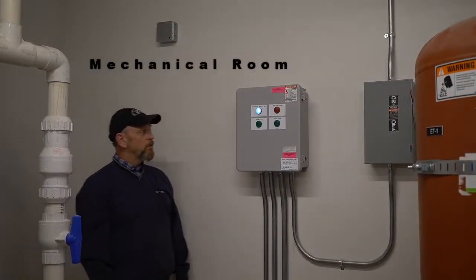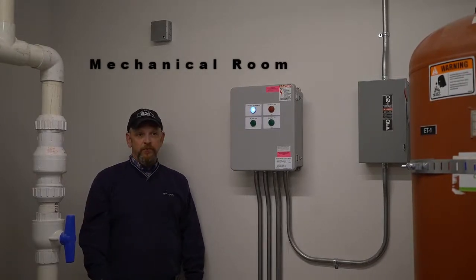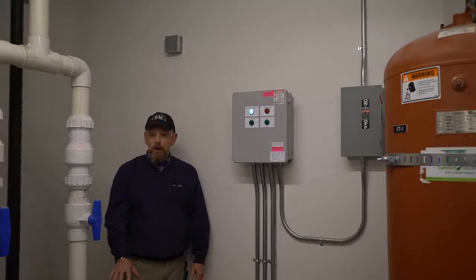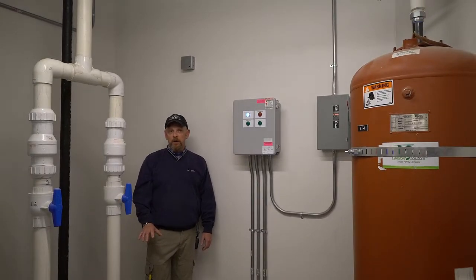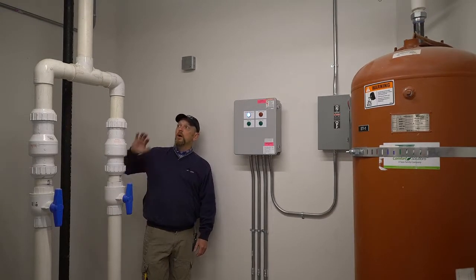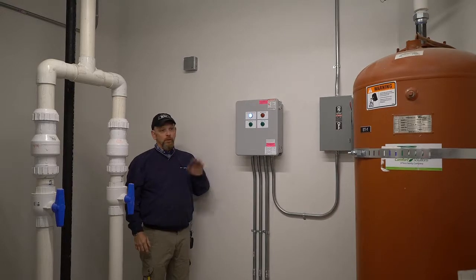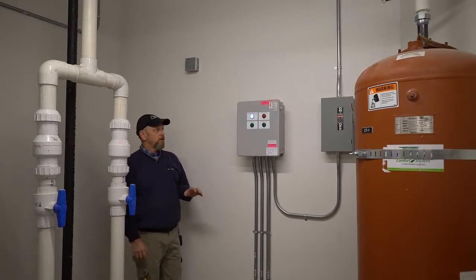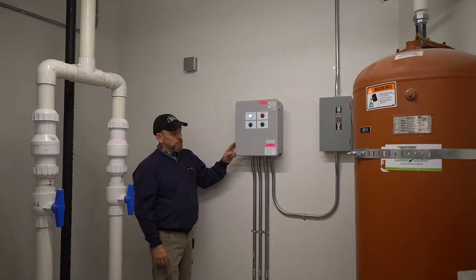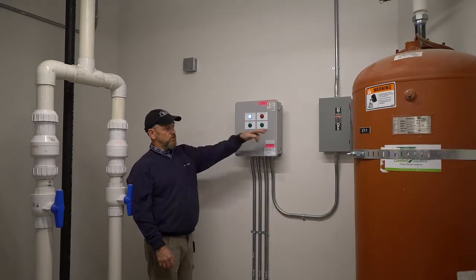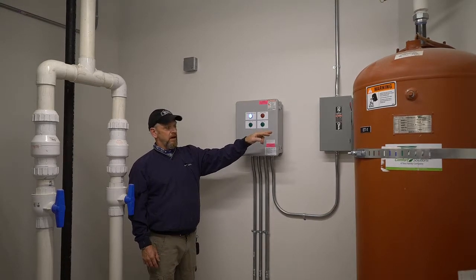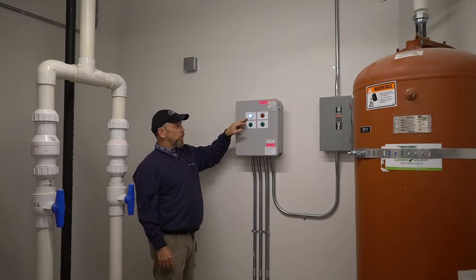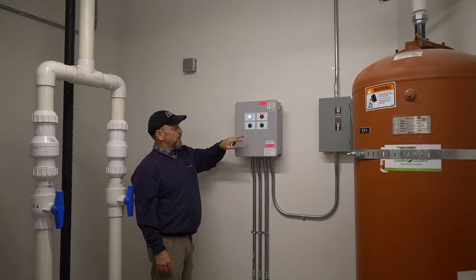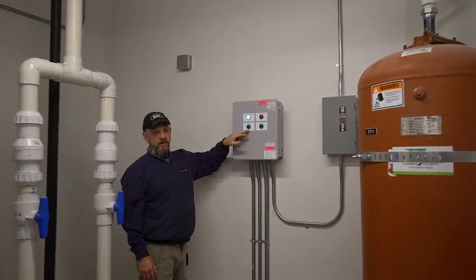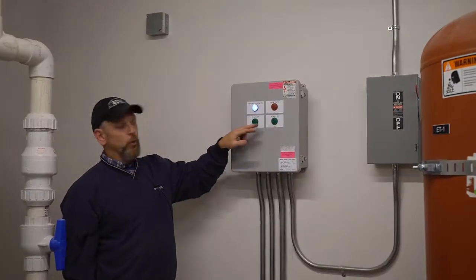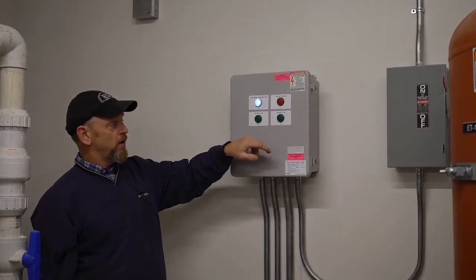So we're in the mechanical room. This is the main sump for the building. There's 2 pumps in here, a lead and a lag pump that will suck the water out of here and take it out. The only thing I wanted to talk about from an electrical standpoint is the control panel. Obviously the disconnect is beside it, has to be on. You can see right now the control power is on, and whenever one of the pumps is activating, you'll see a green light to show you which pump, or maybe they're both on.